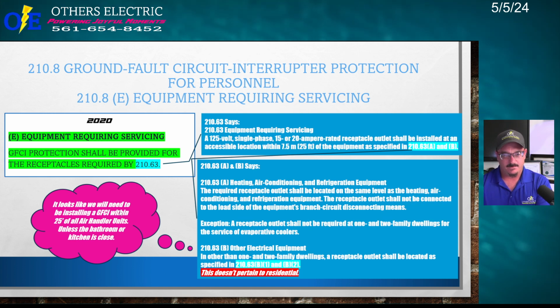So it says here, I just want to note, it looks like we will need to be installing a GFCI within 25 foot of all air handling units, unless the bathroom or kitchen is close. It doesn't say what the GFCI has to be. There just has to be one within 25 foot and on the same level. So that means if the air handler's on the first floor, the GFCI's got to be on the first floor. It can be a kitchen GFI. It can be the bathroom GFI. It just says there needs to be a GFI within 25 foot. Receptacle within 25 foot of the air handler.